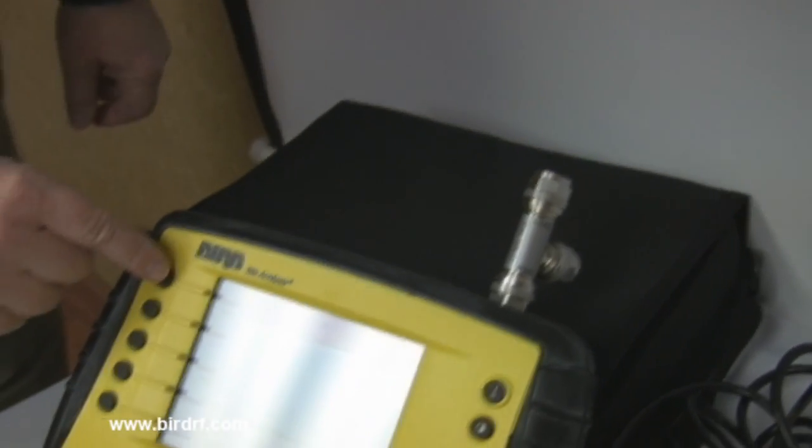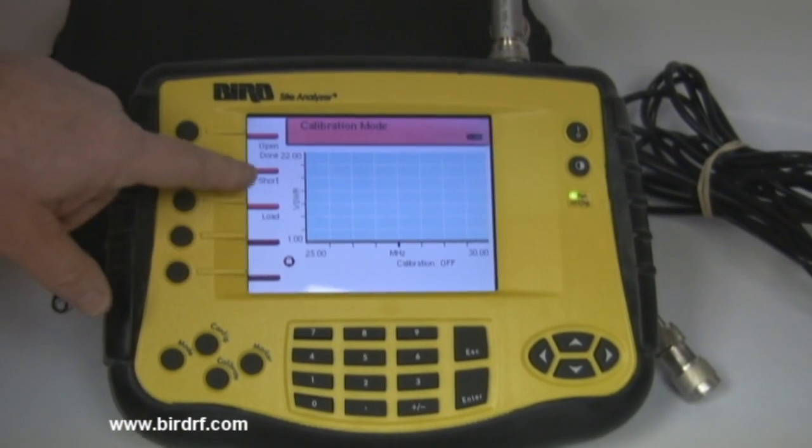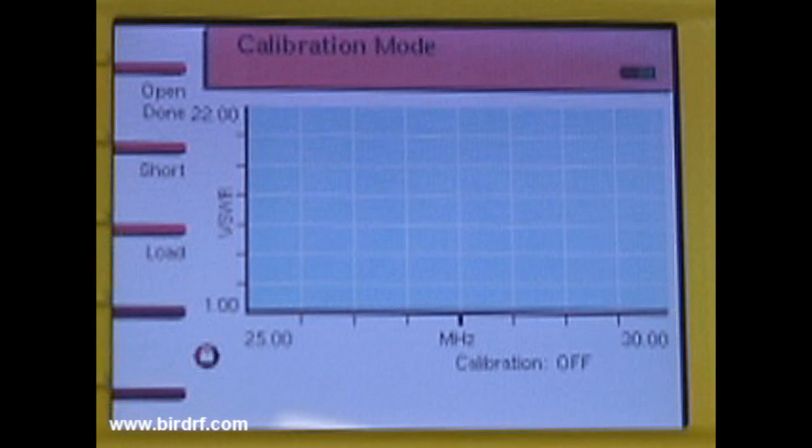Next, connect the cal combo open to the test port of the Site Analyzer and press the open button which is the top button on the left side of the SA screen. Wait for the done indication. This is the notification that the calibration procedure has been performed with the open.